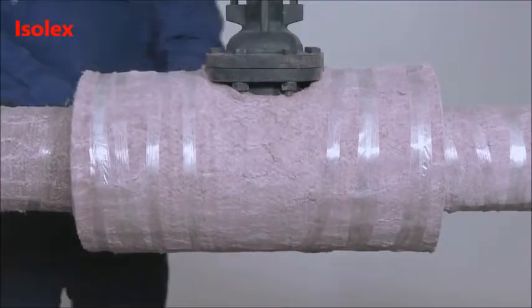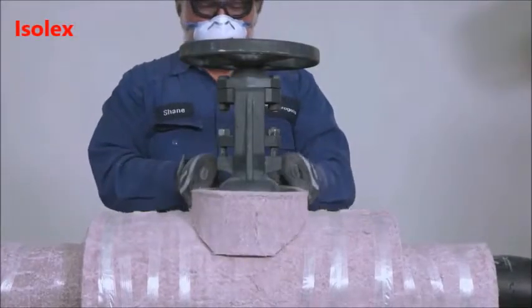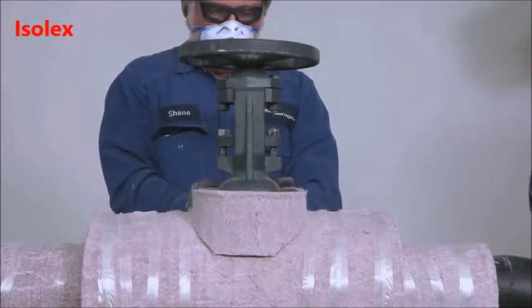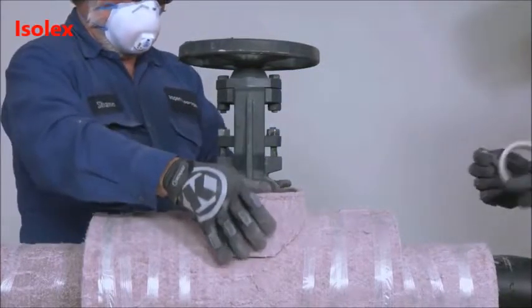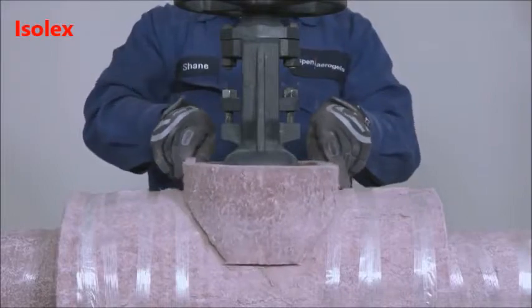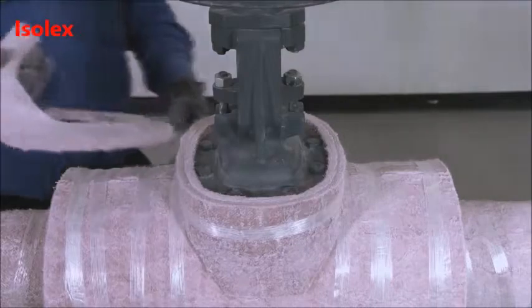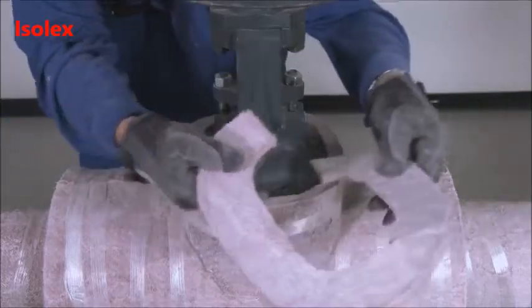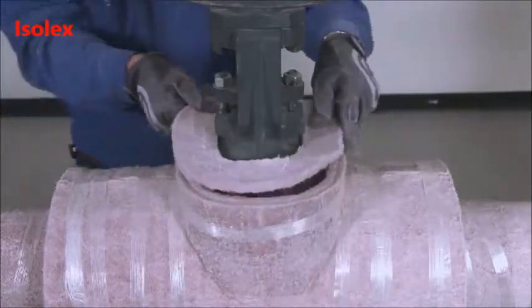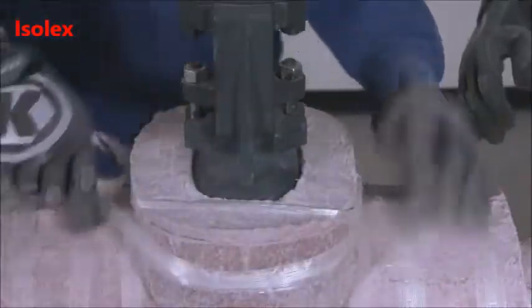Once the valve body insulation is installed, you can now insulate the bonnet area. Wrap the Pyrogel bonnet section around the bonnet area and secure. Continue with additional layers until you achieve the correct thickness. To insulate the top of the bonnet section, cut Pyrogel discs to the same size as the bonnet end. Install the discs on the top of the bonnet section and secure.